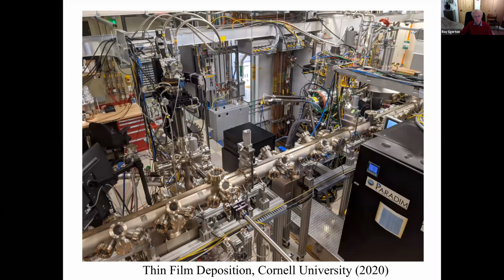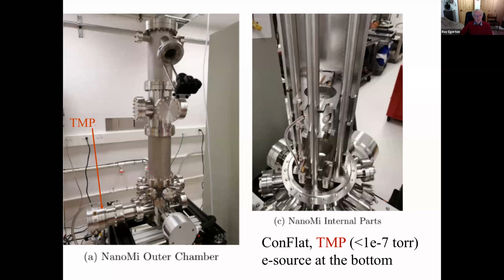So we're talking about this kind of equipment. Here's a complicated example at Cornell University, but our ConFlat arrangement is much more simple. As you can see on the left-hand side, we have a turbomolecular pump connected with these ConFlat flanges to a vertical column. It's all using this stainless steel ConFlat architecture. And on the right-hand side, the internal parts of the column, the electron source is at the bottom. The turbomolecular pump gives us a vacuum of 10 to the minus 7 torr within quite a short period of time.